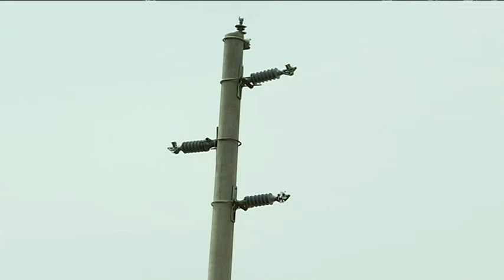We have to do what we call the dry test, which is the process of operating the machine manually, or hydraulically, to see if it will operate. Then finally the wet test, a pre-commissioning test before commissioning, where we open the water and allow it to rotate the turbine to see if it can carry our load. After the wet test, we go ahead with commissioning.